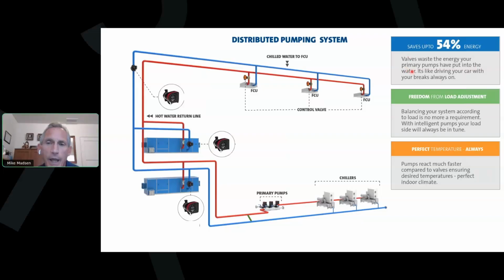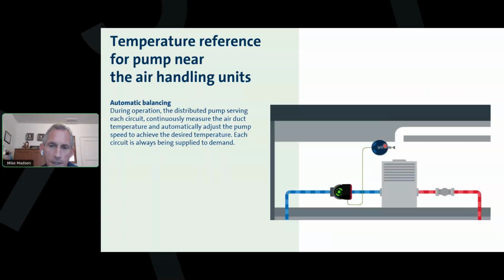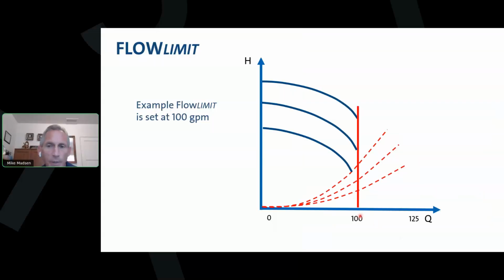So you've got your pump energy savings. We talked quite a bit about the self-balancing nature. So you're going to save time and money on balancing. And then we talked about using the flow limit to give us better delta T control back to the chillers. So like we mentioned, we're going to take that leaving air temperature sensor that's in that air handler already, and we're going to send that 4 to 20 milliamp signal back to the smart pump, and we're going to replace those valves, and we're going to control the flow through the air handler with the pump. I already talked about flow limit. I will set that up in the pumps so that we don't overpump the coil.